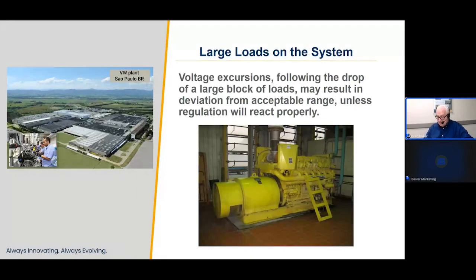If the voltage had been properly controlled, the protective relays would not have tripped the load off, which would have made all the difference in the world. So there are real advantages from the voltage regulation with good responses to changes in the load. And that comes from voltage regulators with high initial response, properly configured and set to hold the voltage within the acceptable range during loss of load.